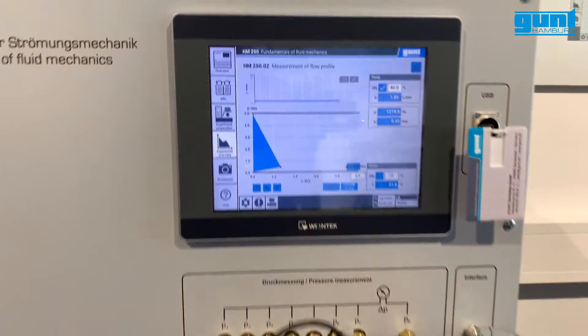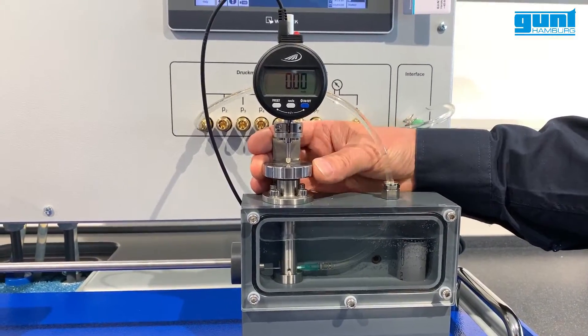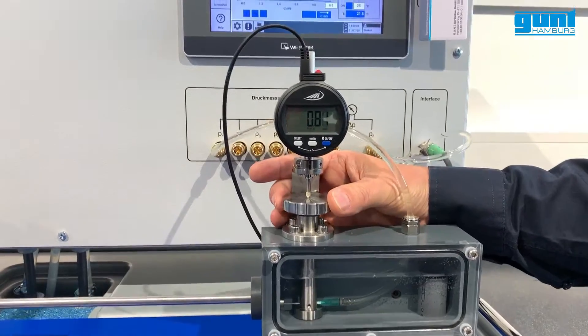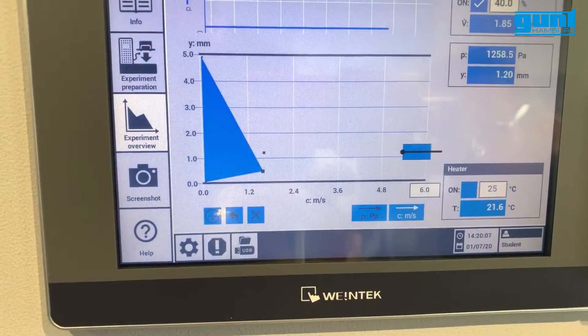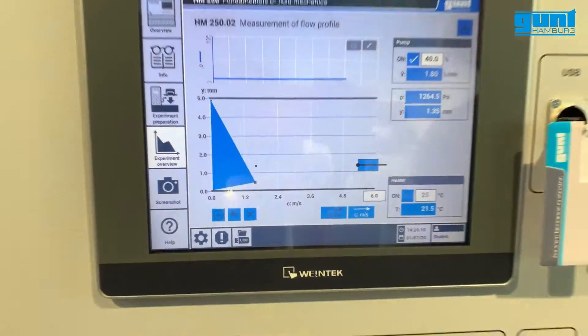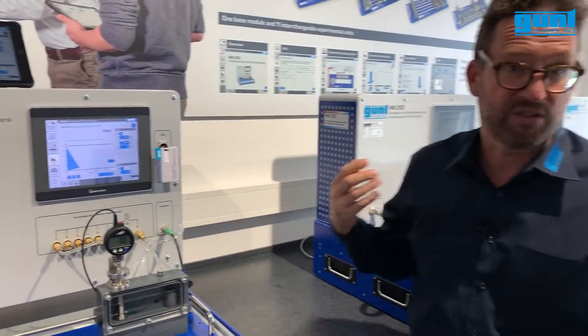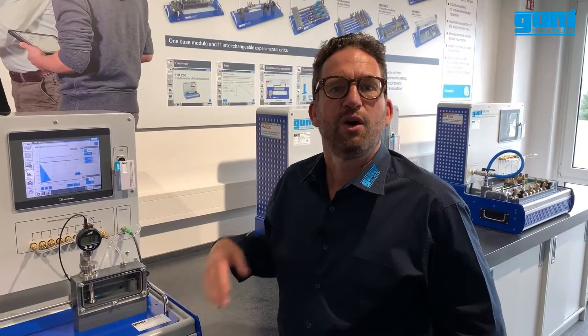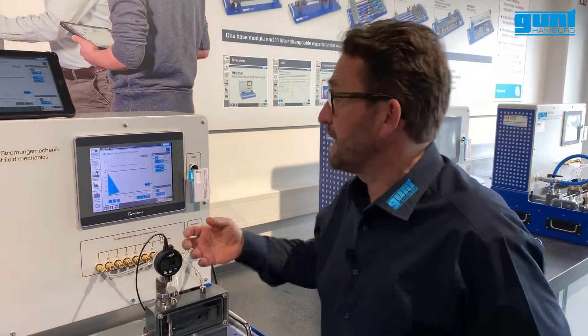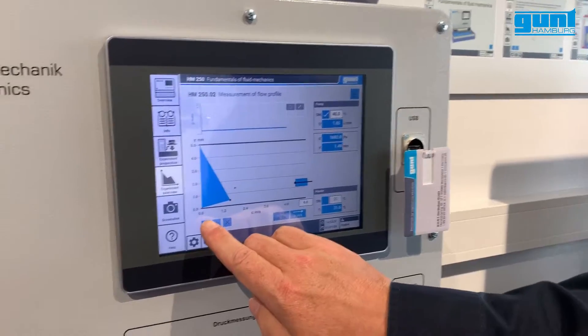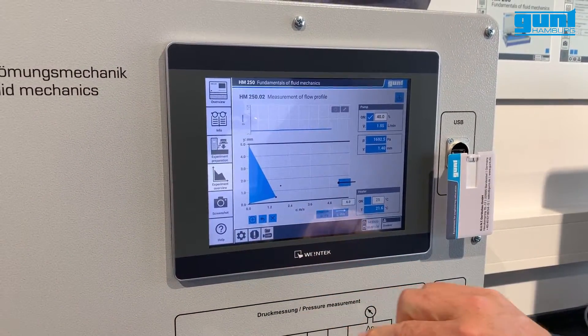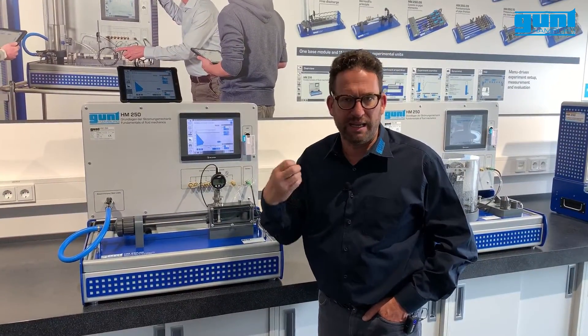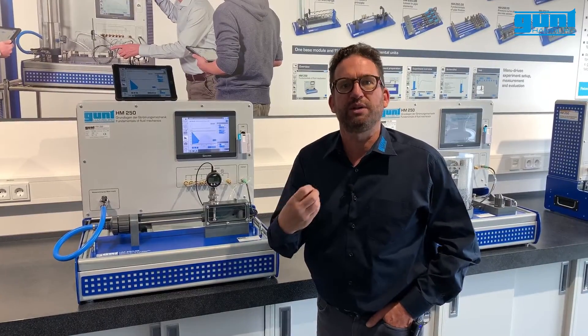Once that's done we can adjust the position of the needle in increments of about one millimeter. It is important to wait until the pressure reading has stabilized again — we suggest about a minute. Once the pressure reading has stabilized, we can plot this measurement point into the graph as well. This step is repeated for as many points in as small increments as you wish until you get a proper graph.